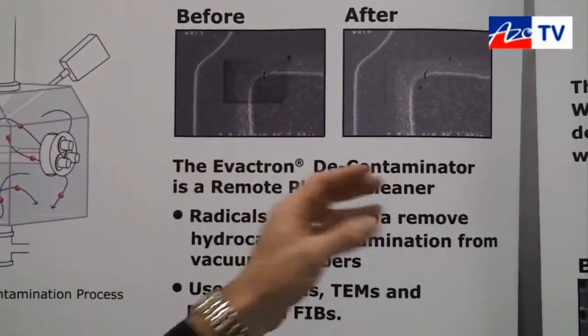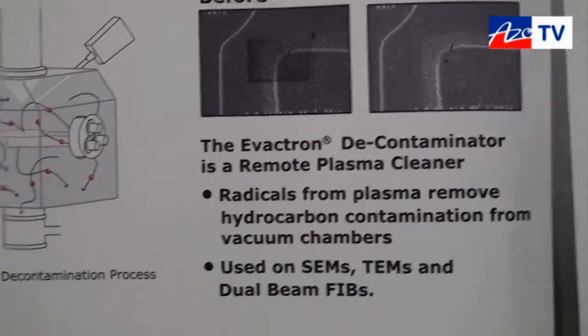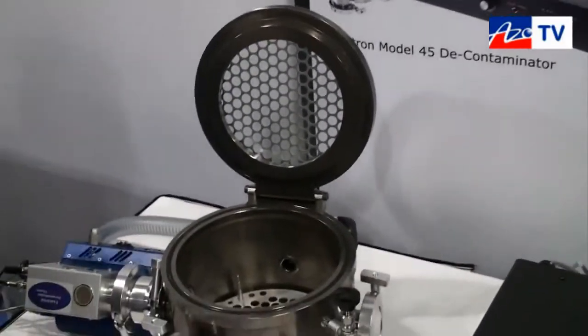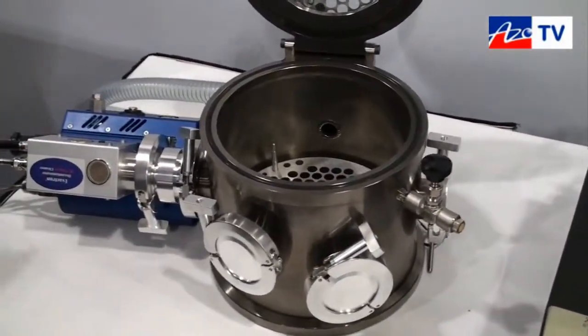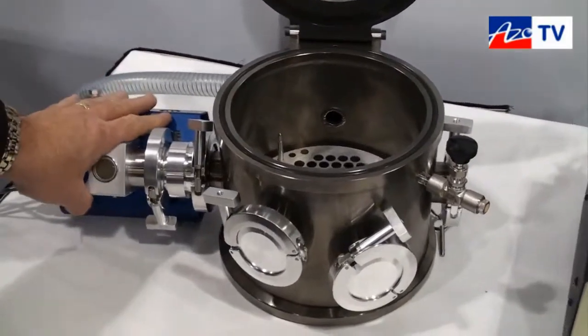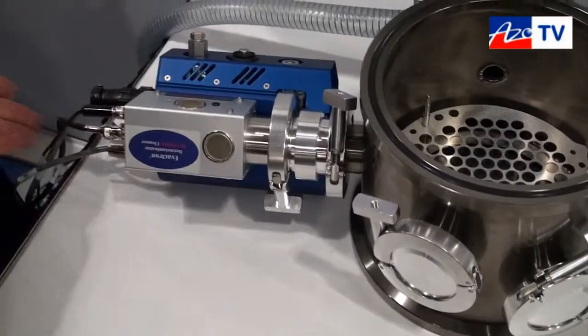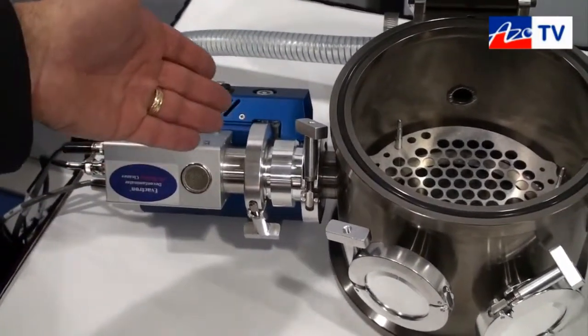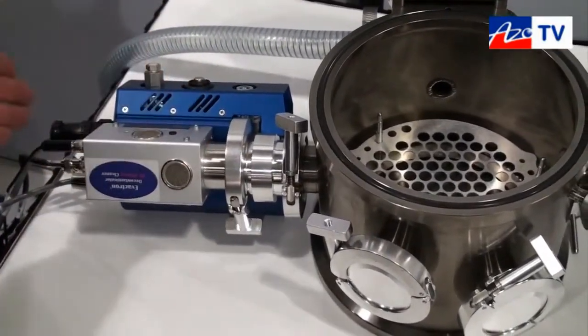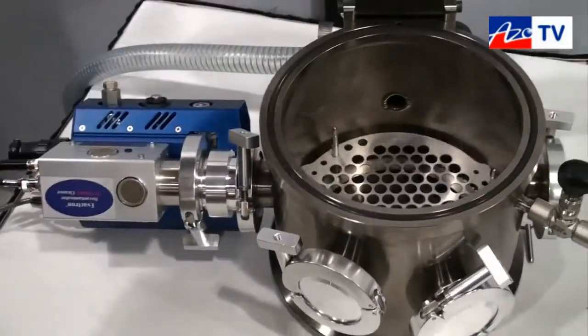That's a before and after picture of a real-world sample. We have over 1,300 of our plasma radical sources installed around the world on a number of different electron microscopes. This is the actual plasma radical source. The gas that we use is most commonly air, so we're using the oxygen radicals in the air to do the actual work. The plasma stays inside here and the gas molecules move into the chamber.